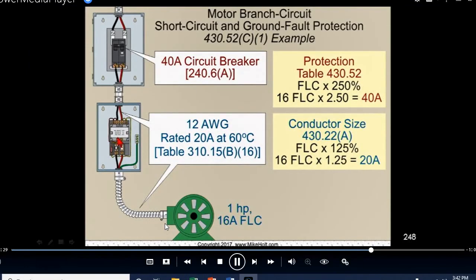And over here, if you take a look at this graphic, we're going to have heaters right here. This provides overload protection. This provides short circuit and ground fault protection. The overload and the short circuit and ground fault combined together provide the protection of the motor. If, let's say, it draws 16 and you draw 22 amps in there, the overload is going to pick this up. It's going to take care of that. But if you have a short, this breaker is going to see that.